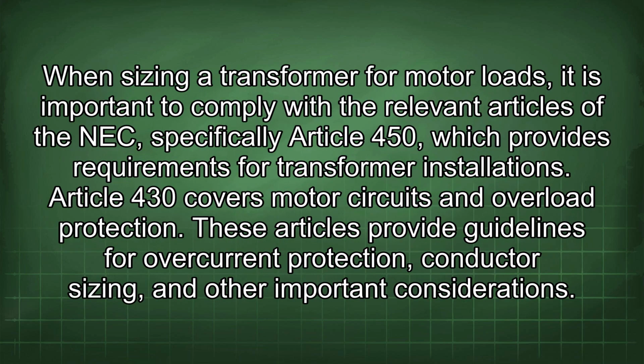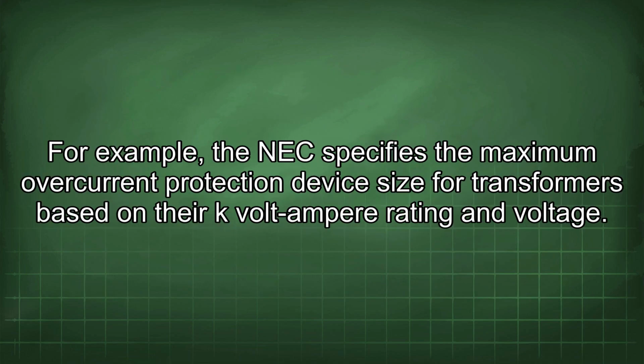When sizing a transformer for motor loads, it is important to comply with the relevant articles of the NEC, specifically Article 450, which provides requirements for transformer installations. Article 430 covers motor circuits and overload protection. These articles provide guidelines for overcurrent protection, conductor sizing, and other important considerations. For example, the NEC specifies the maximum overcurrent protection device size for transformers based on their kV ampere rating and voltage.